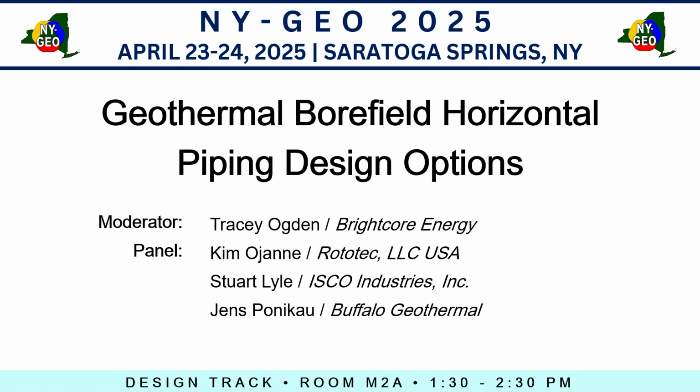No, keep in mind this was actually a relatively large building. This is 250 apartments on there. And so you need a considerable amount of volume. I mean, if you're pumping 250 GPM, the pumps are not the Wilo pumps here. They don't have the pressure to be able to do that at that velocity at peak times through essentially the loop field and the building. That's really the advantage here, that you can separate them.